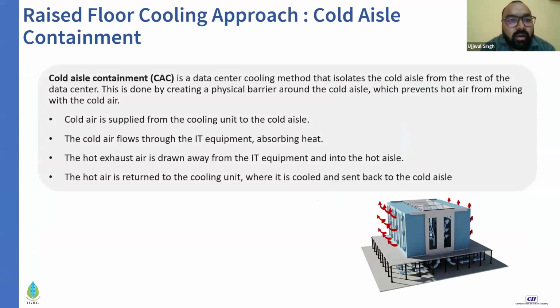Going for raised floor containment, cold aisle containment is the most common technology you must have seen or encountered in data centers. But before going into all the cooling technologies, let me give you the thumb rule: the distance between your cooling unit and your server will determine the efficiency of your overall cooling structure. This is my personal experience that I've understood by studying all these systems.